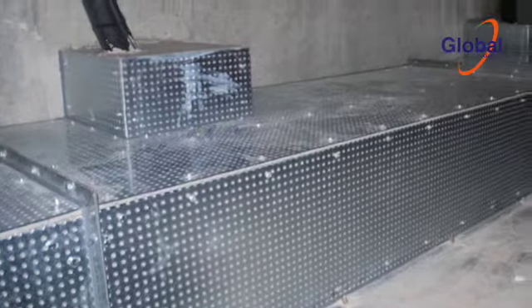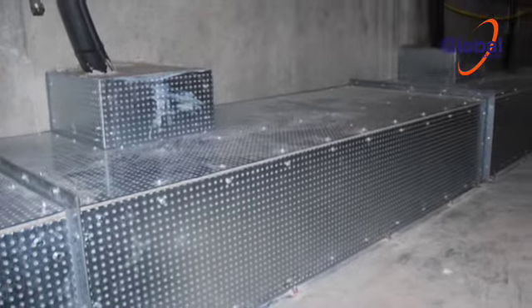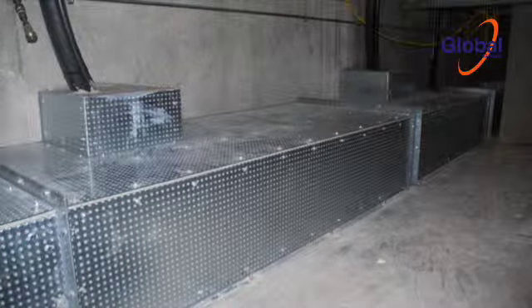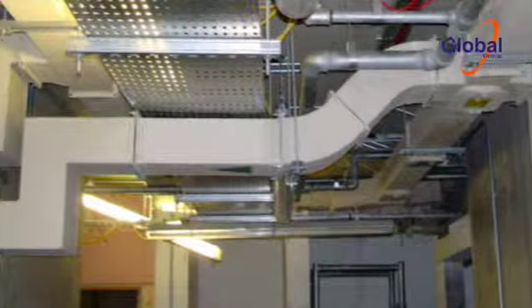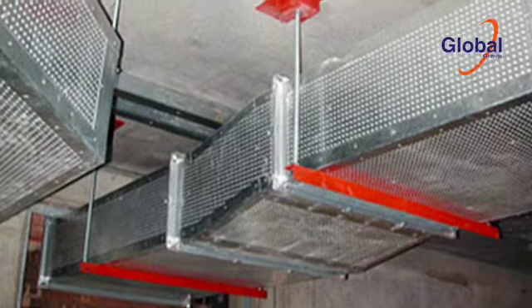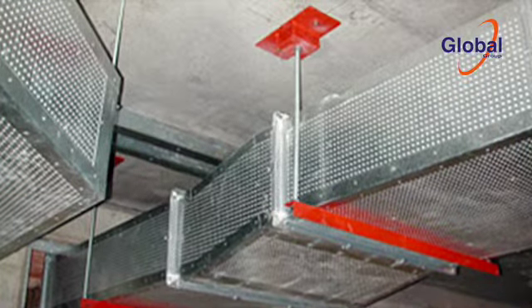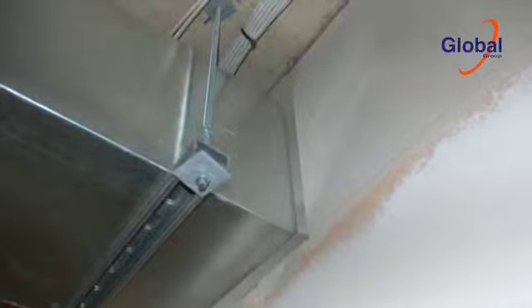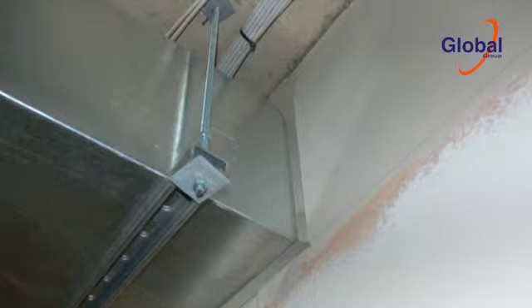If tested and certificated fire-resisting ducts are installed, then fire dampers may not be required. A representative sample of the fire-resisting ductwork should be inspected if installation records are not available. This should be done where the duct passes through compartment walls and escape routes and at other access points. Ductwork must always be sealed and supported on either side of compartment walls or floors to ensure that penetration seals are not damaged by ductwork sagging if a fire occurs.